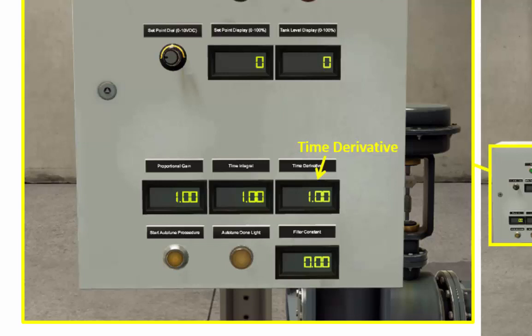Because we're going to use auto-tuning, we should set these gains so that at the beginning they're just set to 1 for the proportional, time integral, and time derivative gains. Then auto-tune will reset those to more appropriate values. This is the filter constant, which is also part of the gains, and the initial value here should be just 0. Then the auto-tune should adjust that as well.